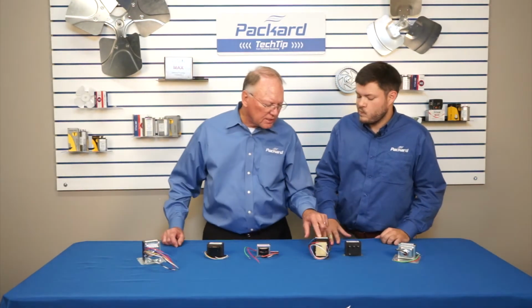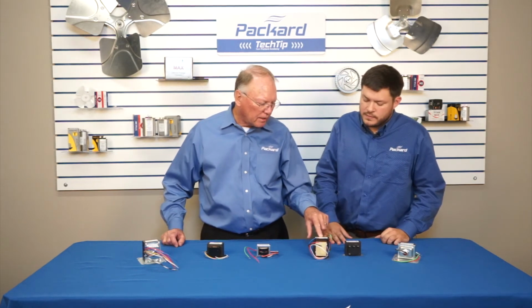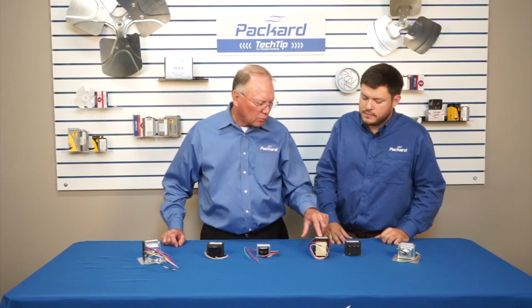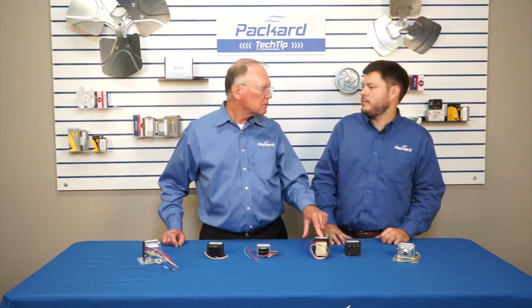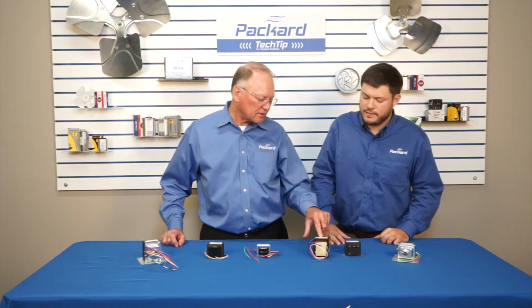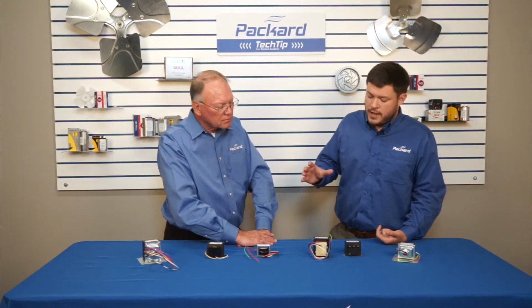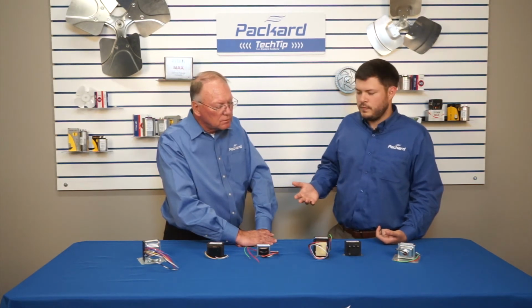So this says 75 VA. That doesn't mean 75 volts AC? It does not, no. So what does that really mean then? 75 VA is the capacity on your secondary side of your transformer. If you have, for math's sake, a 5 amp load on your secondary side, you multiply that 5 amps times your voltage, and that gives you your VA rating.